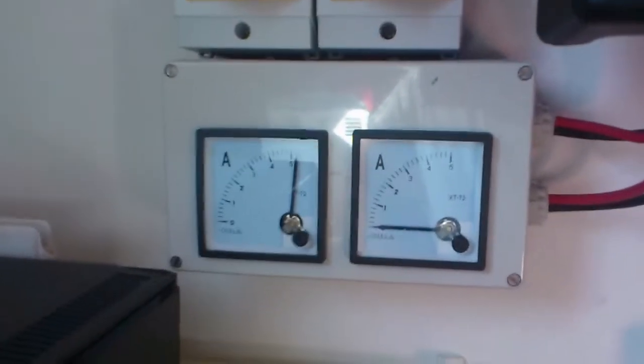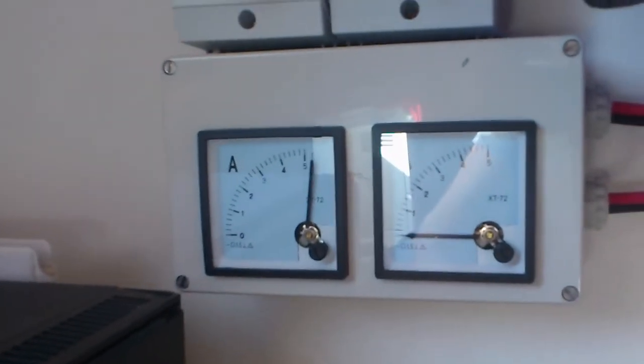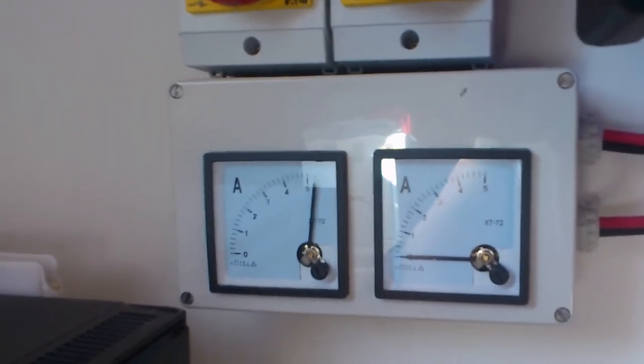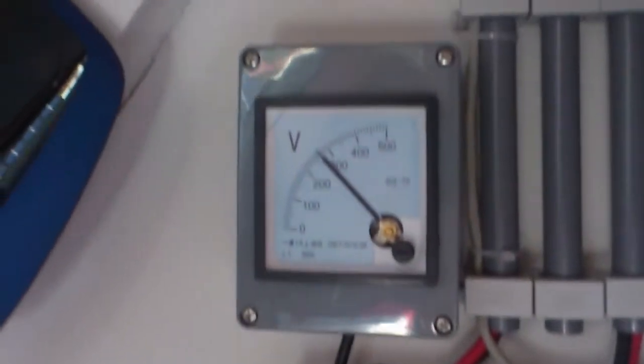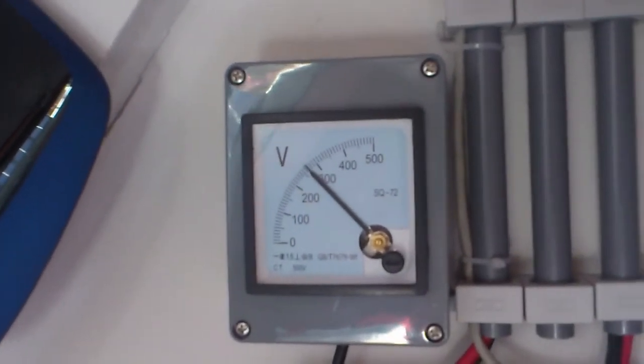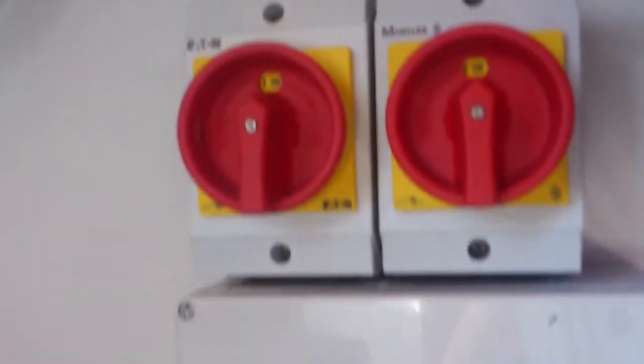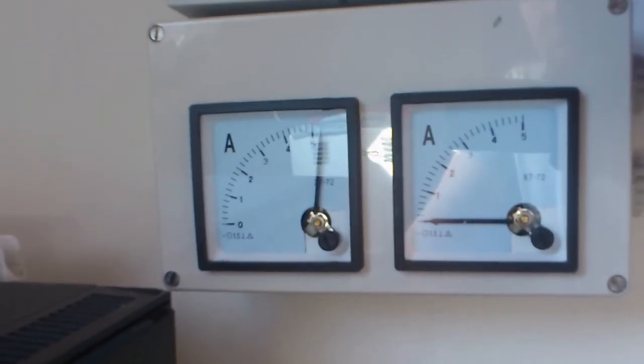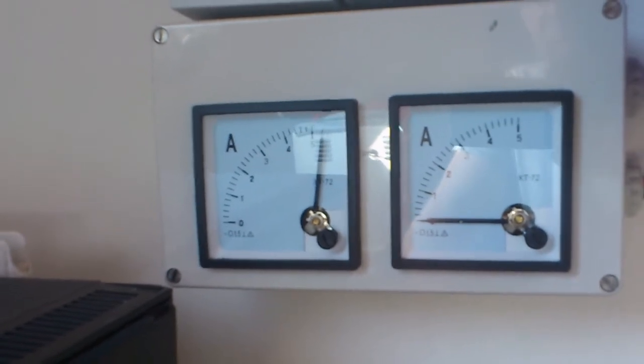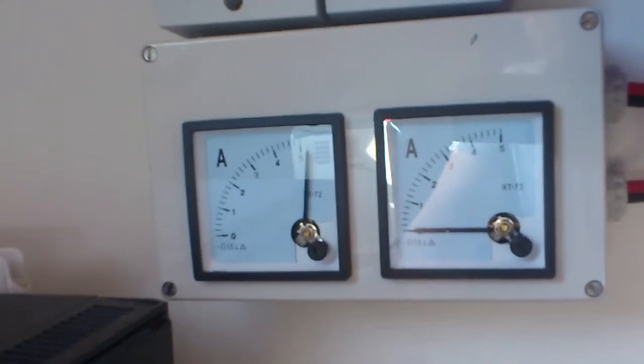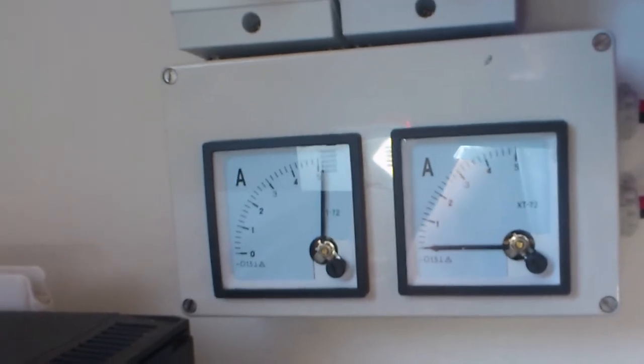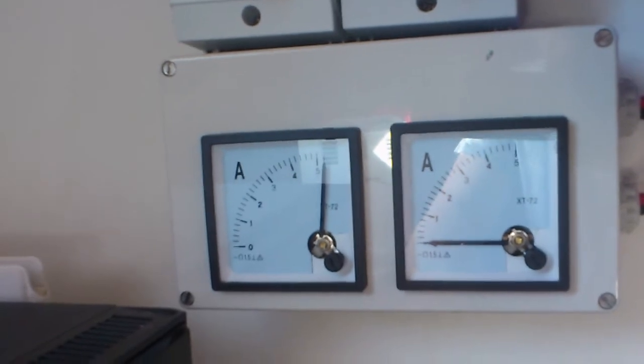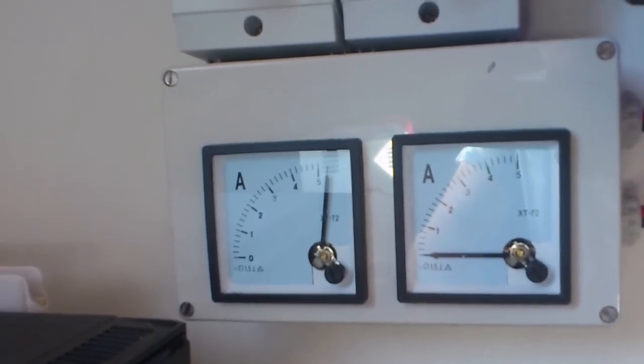And we have the current meters here, and you can see that the voltage mostly remains the same, still about 280, 290. But the current will sag and drop because that's closely tied to the radiation. The actual voltage of the panels doesn't change as much from the starting values until you get actual sunshine on it, which means it actually produces far more current.